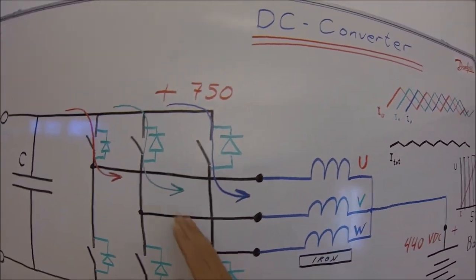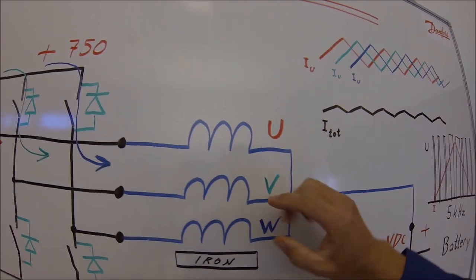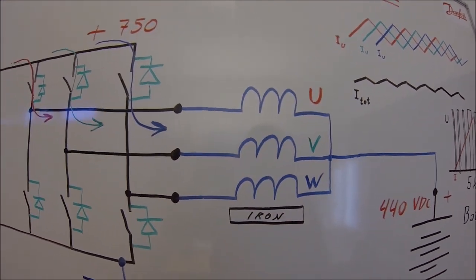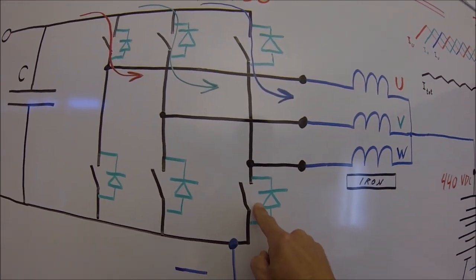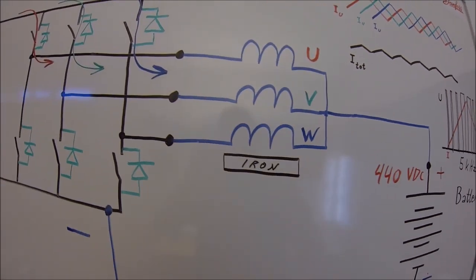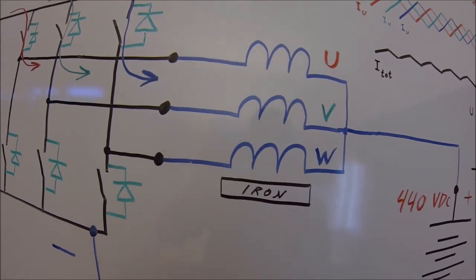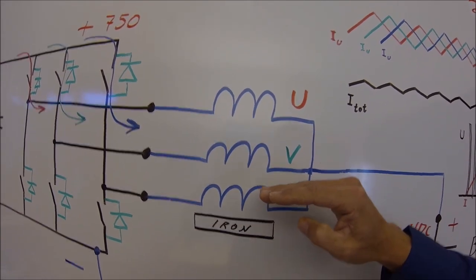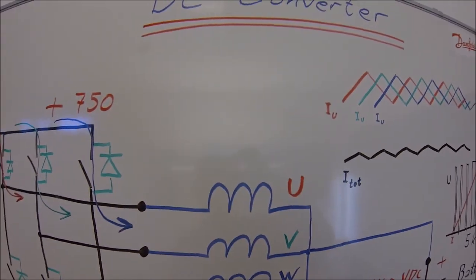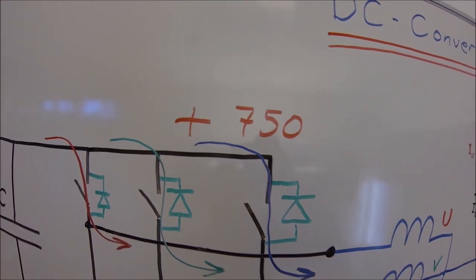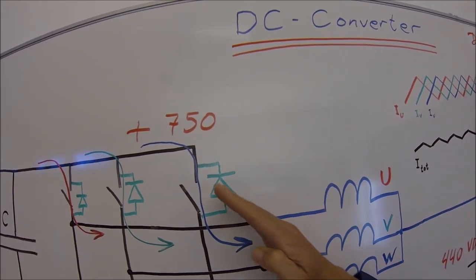What happens with DC boosting is that we set up a small current through the chokes. We saturate the iron and then we cut off the current. We connect these IGBTs, so this potential is the same as this potential. The current is then stopped quite abruptly and the voltage will increase quite rapidly over the chokes. So we are boosting the DC voltage level here.